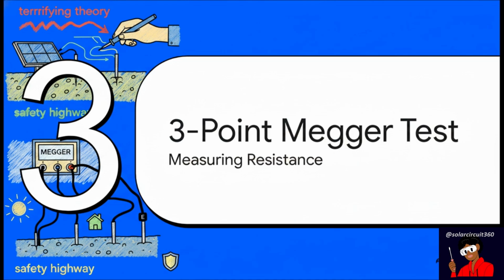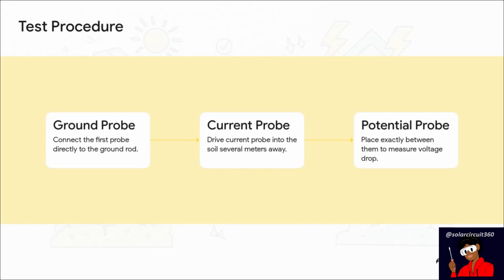Let's move to Section 3, the three-point Megger test. Now what's really interesting here is that we're shifting from the theory of faults to the actual, hands-on practice of measuring your safety highway. You can't just guess your resistance. You need specific equipment, specifically an earth tester known as a Megger. The physical steps are super precise. Step 1, you connect your first probe directly to the ground rod.